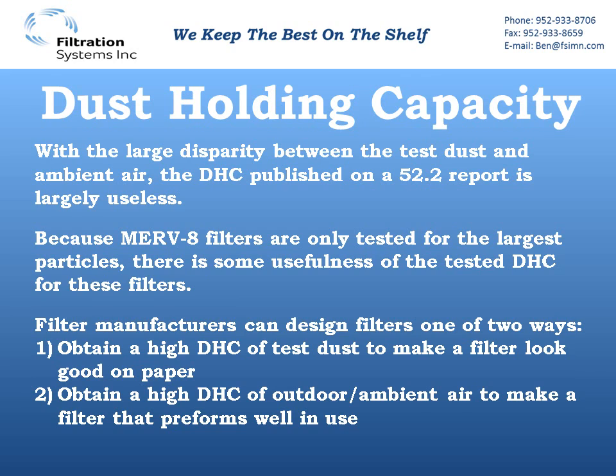There is one caveat for MERV-8, and that's because MERV-8 is only tested at the large particle size range of 3 to 10 microns, so there is some limited value there for MERV-8. But when we get into higher efficiency and more critical applications, it gets to be difficult.